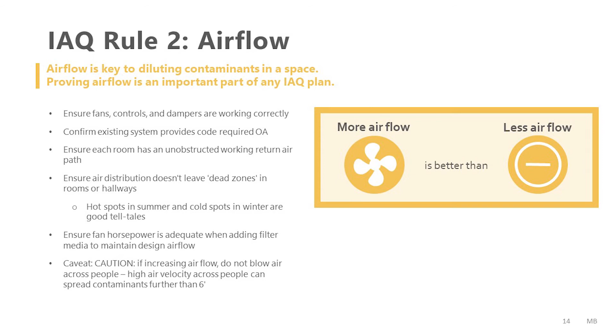And finally, one caution: every rule has exceptions. One of the things we do not recommend is blowing air across people in a classroom or an auditorium or a gym. Higher velocity airflow can actually carry particles and droplets further than they would naturally travel. So for instance, if we have people spaced 6 feet apart and then we're blowing air across them at a higher velocity, you can actually transmit a pathogen or respiration product further than you would have done. So be careful about increasing velocity across people.